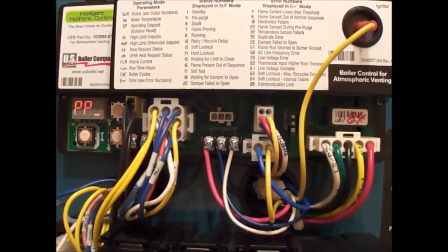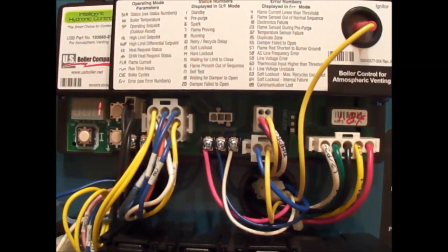We have to use residual heat first. Turn the pump on, let it run and drop the water temperature below 140, then fire the boiler. If the boiler is less than 140, it can fire up as soon as we check the water temperature and make sure it's not above 140.